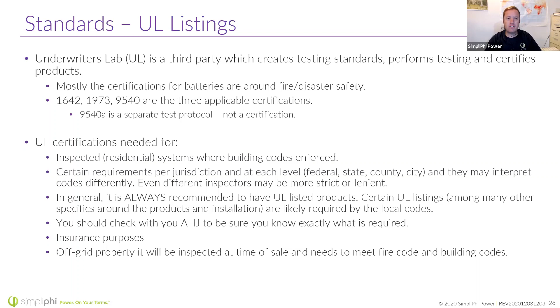You're always going to want to see these UL listings, even if you're off-grid, to sell the system. If you're having the system inspected, your authority having jurisdiction or inspector will probably look for this UL listing — always check with them beforehand so you know what they'll be asking for. You don't want to wait until the end of the day to find out the equipment you bought doesn't have the UL listing and now you're failing inspection.